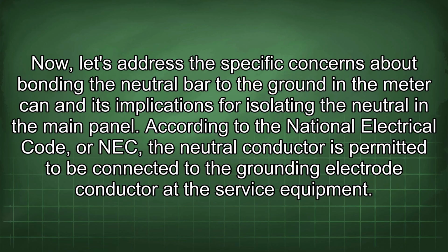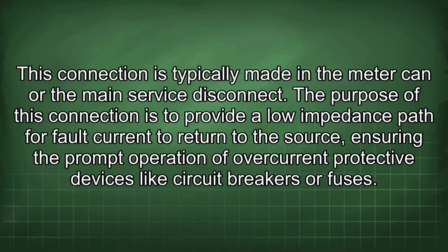According to the National Electrical Code, or NEC, the neutral conductor is permitted to be connected to the grounding electrode conductor at the service equipment. This connection is typically made in the meter can or the main service disconnect. The purpose of this connection is to provide a low impedance path for fault current to return to the source, ensuring the prompt operation of overcurrent protective devices like circuit breakers or fuses.